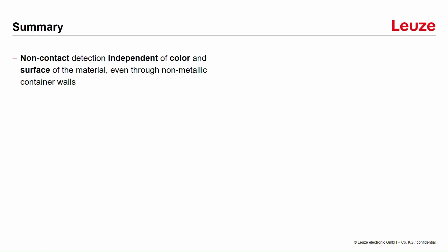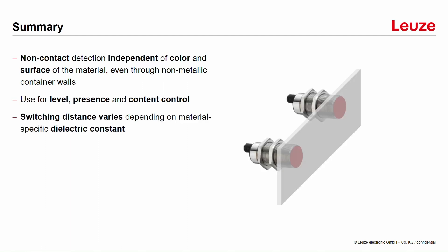Let's sum up the main facts for capacitive sensors. With this sensor technology it is possible to detect materials completely independently of their color and surface, even through container walls. These sensors are very useful for applications with level, presence, or content control. It is very important to consider that the switching distance varies depending on the material-specific dielectric constant. For dry materials, for example sugar, the dielectric constant is very low and therefore the switching distance will be low. For materials with a high share of water, the switching distance will be higher.